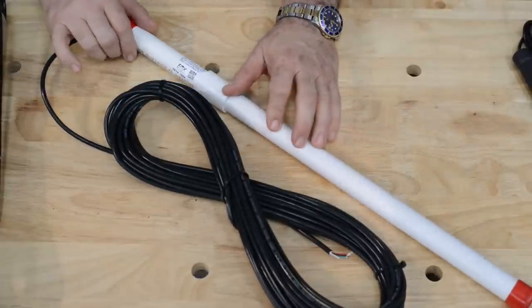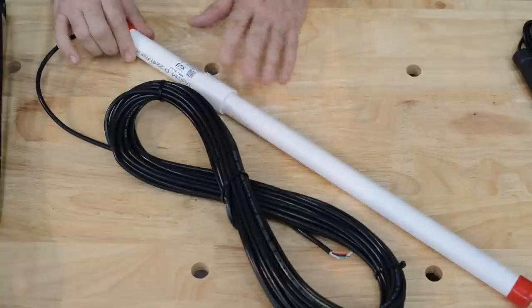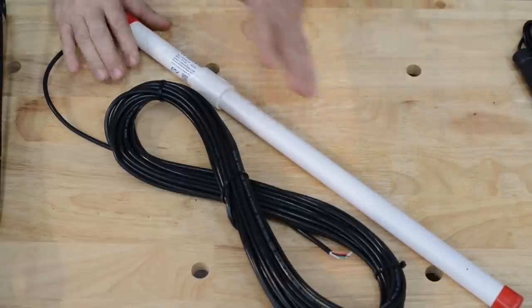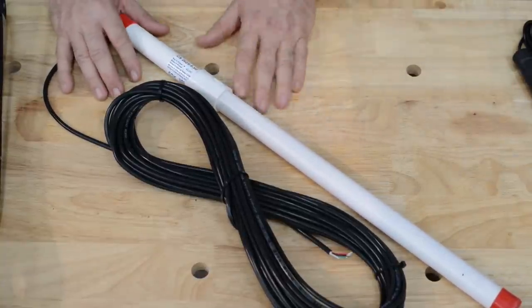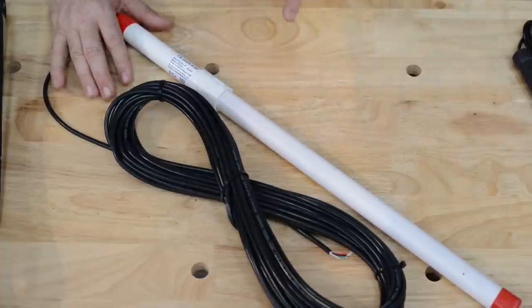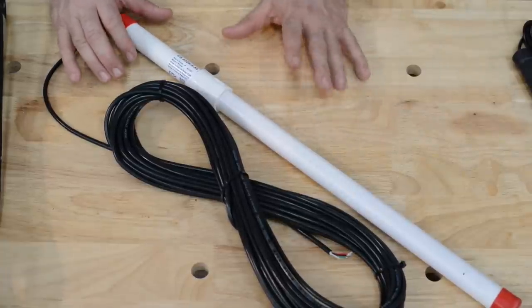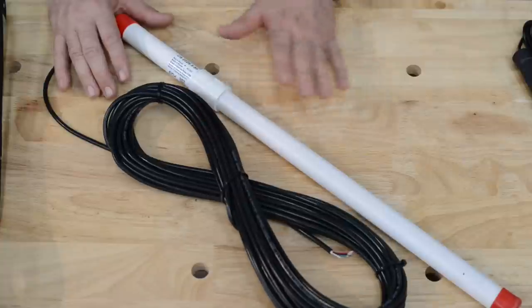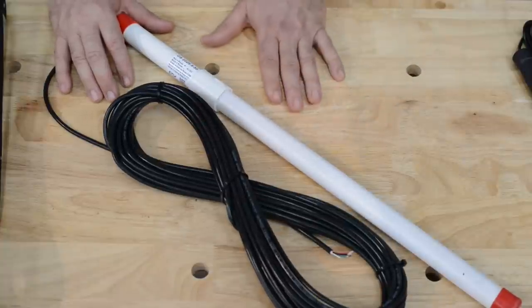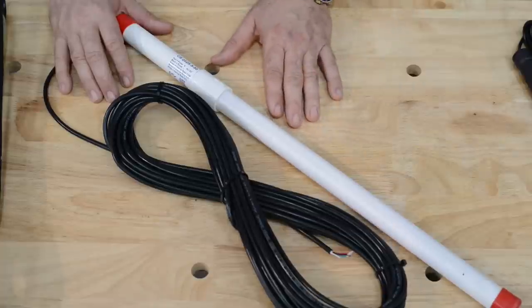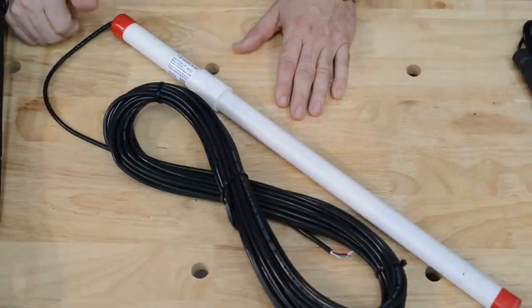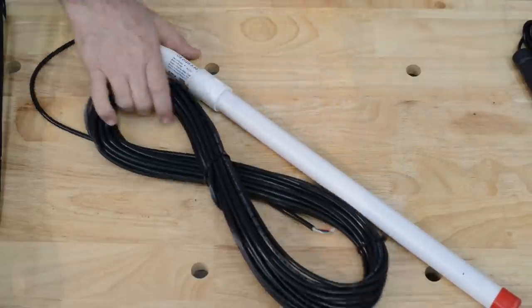This is the Gatecrafters one. It's manufactured for us by EMX. This is the original one. This is what's been around for years. It's a good, reliable exit wand. And I recommend it in a lot of different circumstances. But I don't recommend it in lightning prone areas. They don't survive the lightning as well as some of the other ones you're going to see. But other than that, it's a pretty reliable unit.